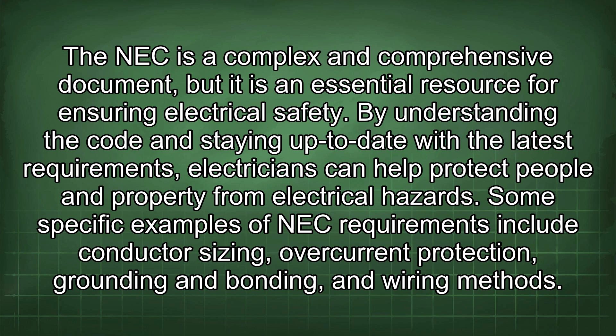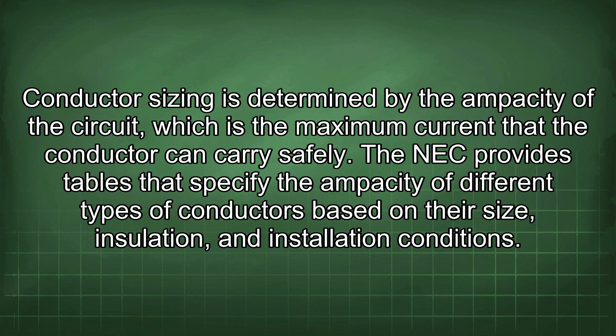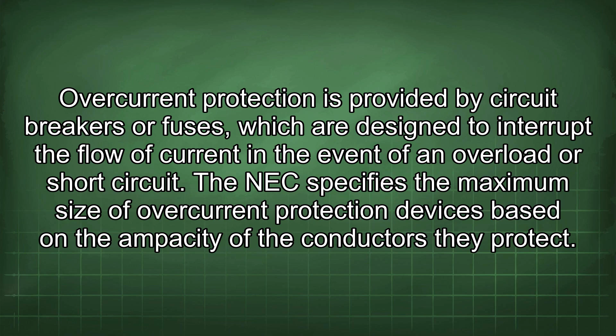Conductor sizing is determined by the ampacity of the circuit, which is the maximum current that the conductor can carry safely. The NEC provides tables that specify the ampacity of different types of conductors based on their size, insulation, and installation conditions. Overcurrent protection is provided by circuit breakers or fuses, which are designed to interrupt the flow of current in the event of an overload or short circuit. The NEC specifies the maximum size of overcurrent protection devices based on the ampacity of the conductors they protect.